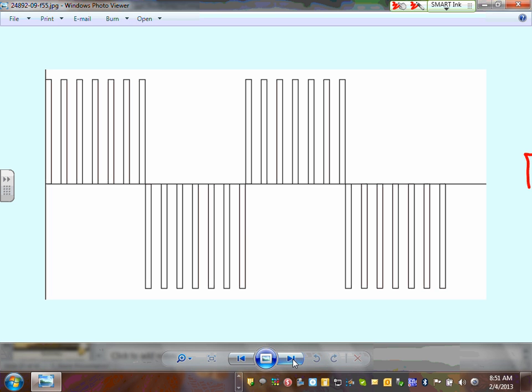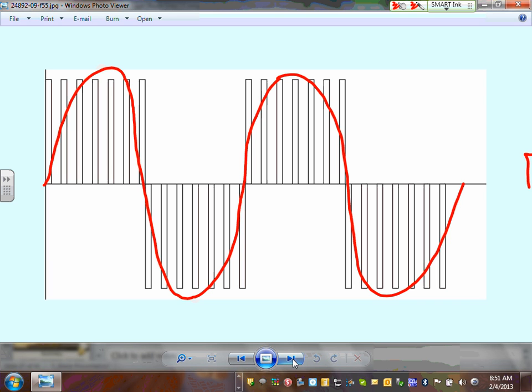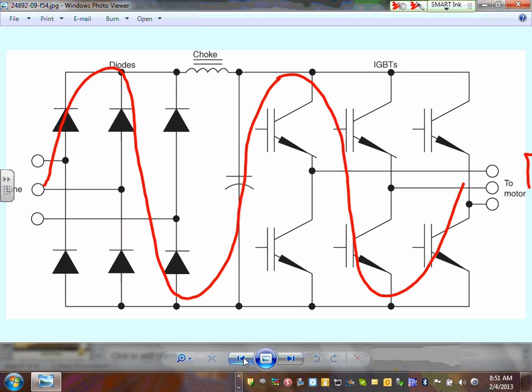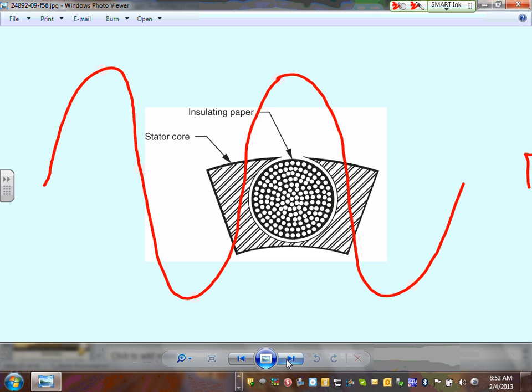Look at the pulsation. As far as your motor is concerned, this is nothing but an AC signal. Your motor will be cheated into thinking that this is an AC signal. Does that make sense? So that's the best technology you can use, which is these IGBTs. Because of all this, everybody's cool with IGBT technology in VFDs, everybody's cool with an AC drive, which is the frequency drives, and DC drives, which is to drive the DC motors. That's really what we're going to do.